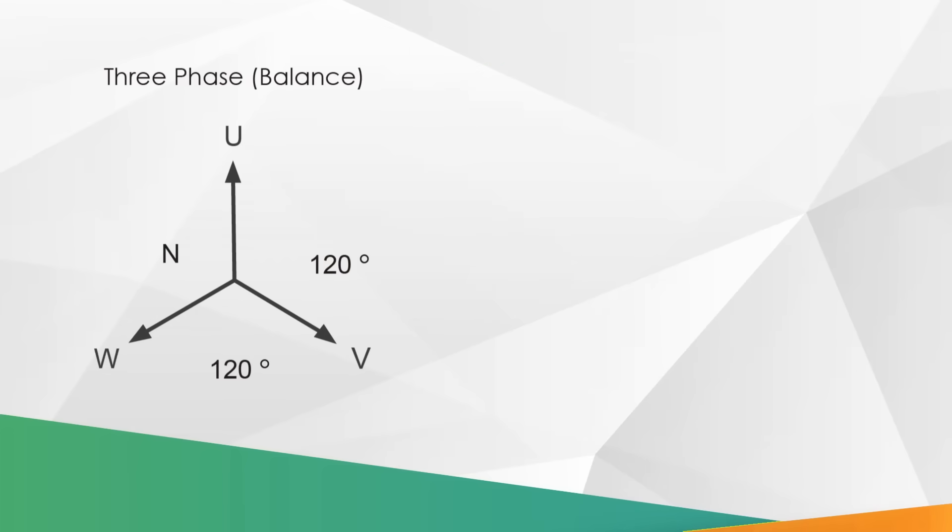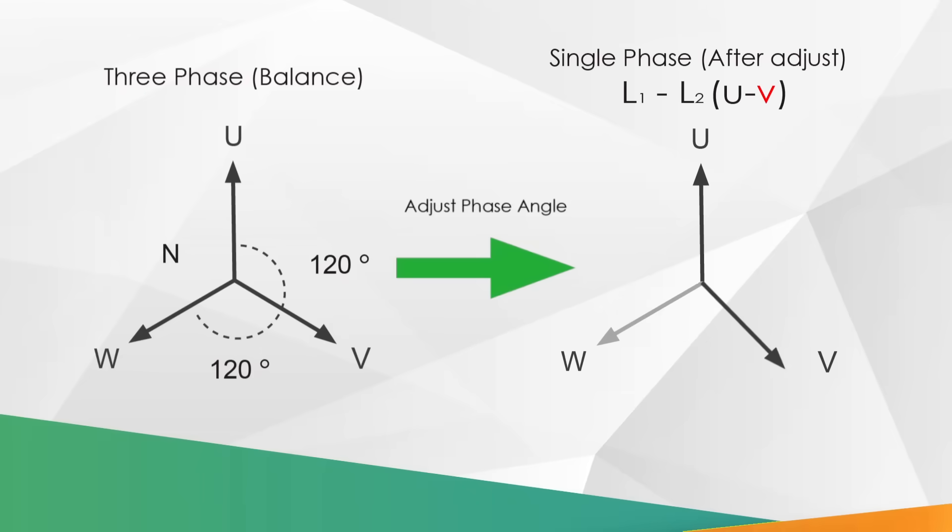Generally speaking, when three-phase is under balanced situation, the phase angle between phase to phase is 120 degrees. To test single-phase three-wire load, you have to adjust the angle to 180 degrees and connect the two-wire line-to-line at the output terminal.